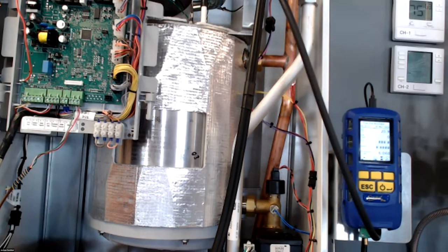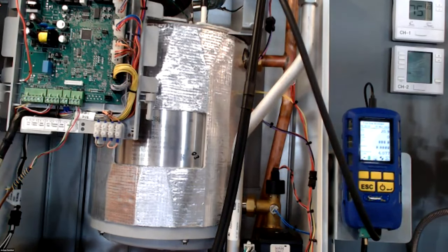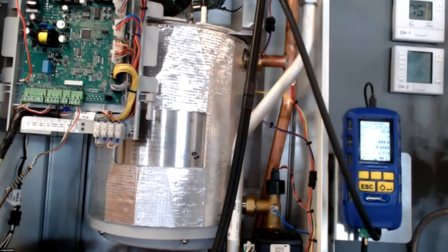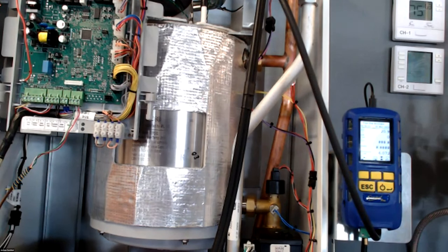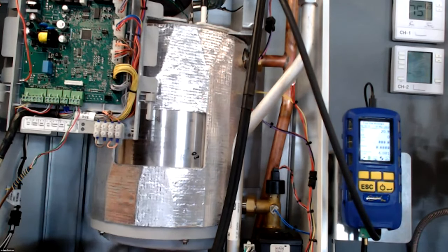exceeding the length. I've seen it happen on delayed ignitions with ignition issues, but usually it was a grounding problem or an installation error. They dropped wiring on the grounding. We're having delayed ignition. Gas pressure issues can cause that, too much gas pressure. So there's a lot of things. I'd have a lot of questions on that specifically. Okay, so if that issue does come up in the field, we'd highly recommend calling into the Triangle Tube tech support line and addressing it. 100%.